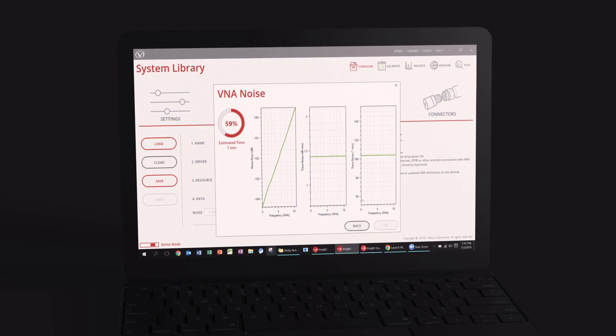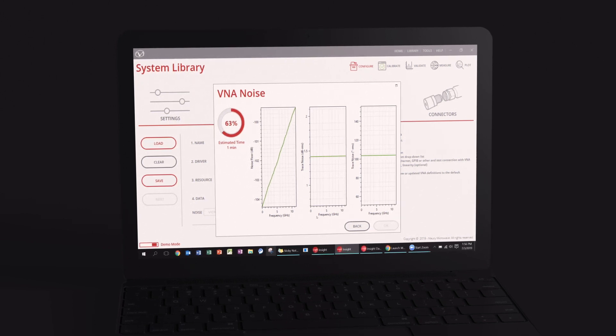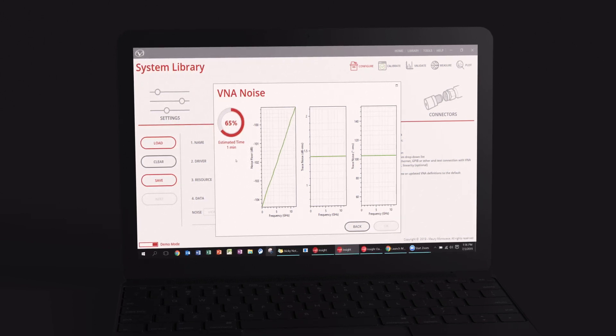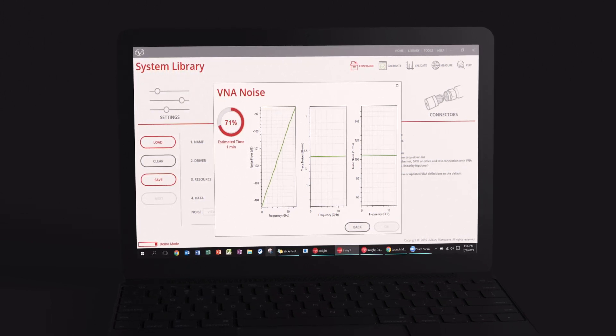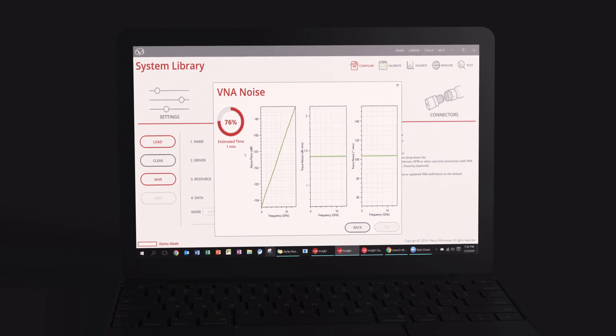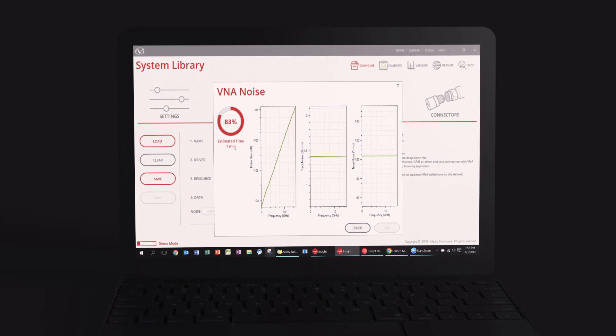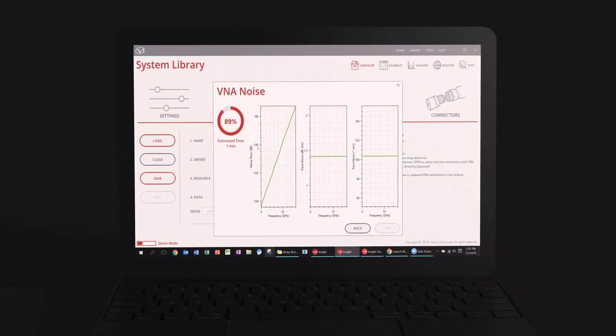Starting with the VNA, users can characterize the uncertainty for the specific settings used to measure their device under test, including IF bandwidth, port power, and averaging. VNA uncertainty is related to the VNA noise floor, including the noise floor itself.